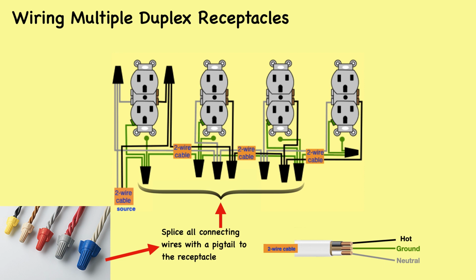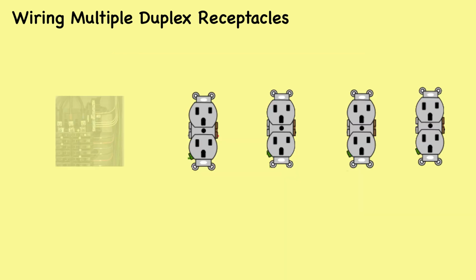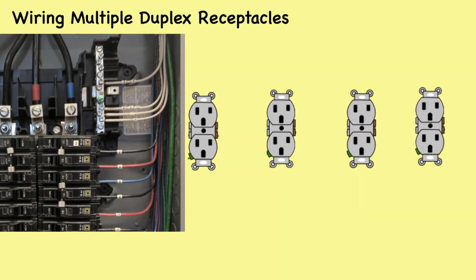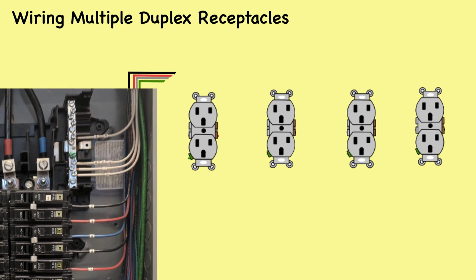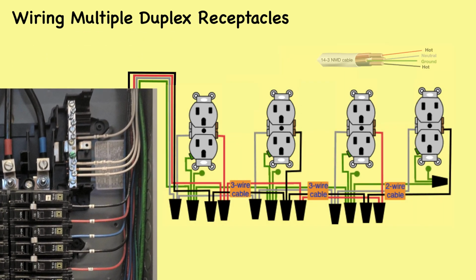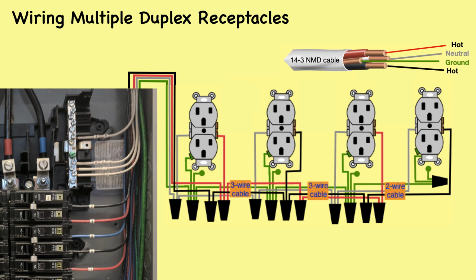This wiring allows for source voltage at each outlet independent of the others in the circuit. Here, a 3-wire cable is run from a double pole circuit breaker providing an independent 120 volts to two sets of multiple outlets. The neutral wire from the circuit is shared by both sets. This wiring is commonly used in a kitchen circuit where two appliance feeds are needed, such as a refrigerator or microwave in the same location and/or countertop receptacles.